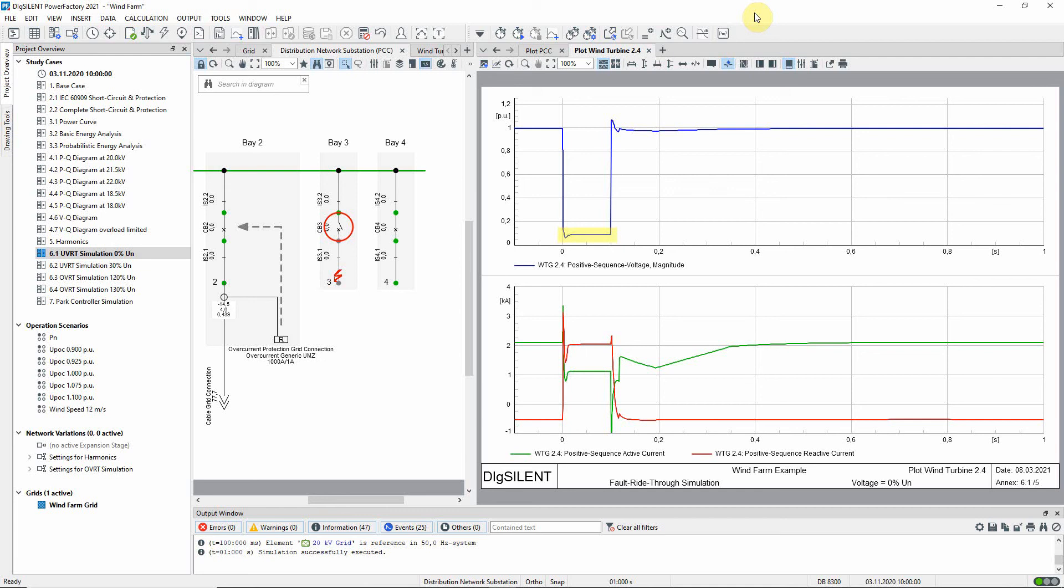But the voltage does not collapse to zero, as at the point of common coupling, because of the impedance between that point and the turbine. In the bottom plot, the active current supplied by the turbine is shown in green, and the reactive current in red. It can be seen that prior to the fault, the active and reactive current are constant.